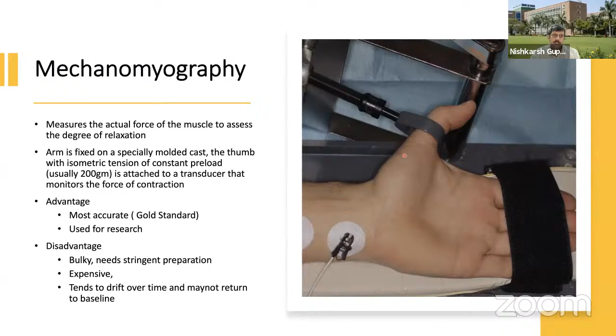The advantage of mechanomyography was that it is most accurate. So it is considered the gold standard and is basically used for research. You may find them in physiology labs in our setups. The disadvantage is it is bulky, expensive, and the problem is that it tends to drift over time and may not return to baseline. So it becomes difficult to actually follow monitoring on this device.